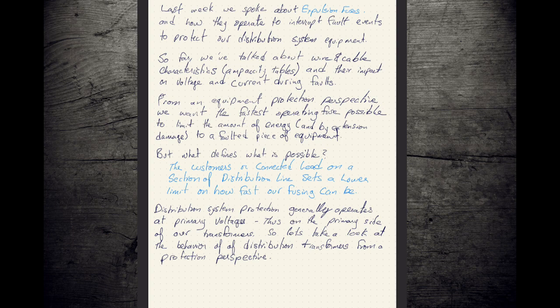And so, from an equipment protection perspective, it'd be really great if we didn't ever have any load current, right? We'd like things to go as fast as we can possibly make them go. And as soon as there's any sort of current flowing, just put the brakes to it. But if we did that, we wouldn't have a very useful distribution system. So, we stand by the principle we want to operate as fast as possible, but what really defines fast as possible? And that is our customer loads.